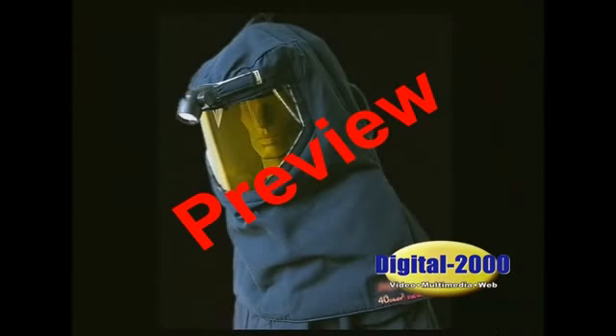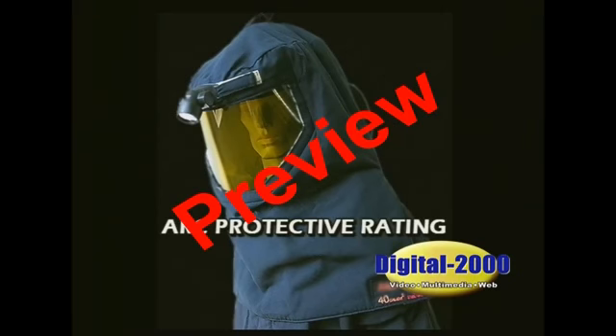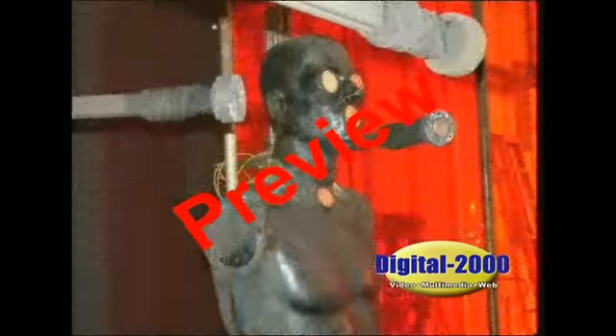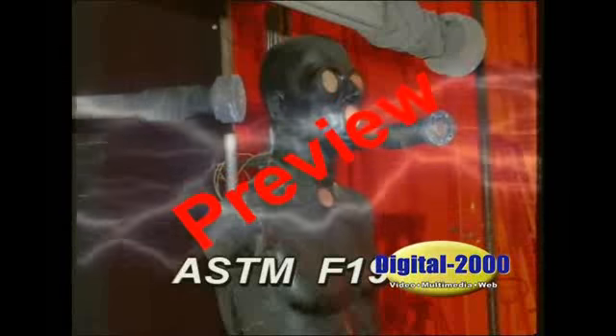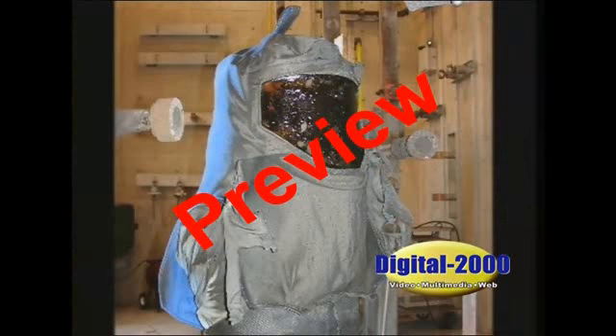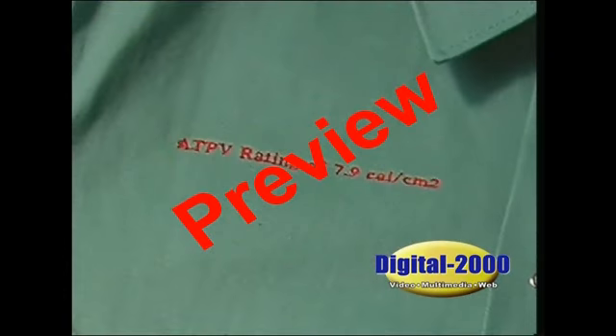NFPA 70E and ASTM F1506 require that an arc flash garment be marked on its label with its specific arc protective rating. This will state in black and white the level of the protective characteristic of the product against an arc's energy. This arc rating is determined by a specific test procedure, ASTM F1959, where an arc flash is created in laboratories to simulate real-world conditions. Under these conditions, the protective characteristics of the material from which the garment is made is determined. Without this arc rating, the garment is simply a work shirt and should not be used as arc flash protection.